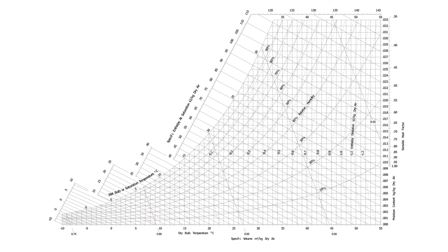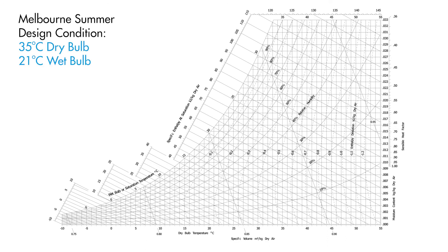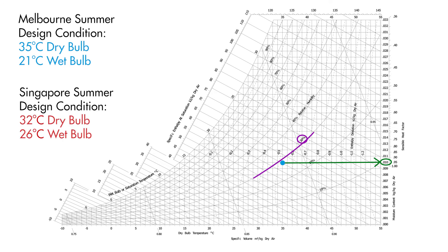Now that we understand these lines of the chart, let's plot the Melbourne summer design condition of 35 degrees dry bulb and 21 degrees wet bulb on the chart. From this point we can immediately see this has a relative humidity of just under 30% and a moisture content of around 10 grams per kilogram of dry air. In comparison, the much more humid Singapore design condition of 32 degrees dry bulb and 26 degrees wet bulb has a relative humidity of a bit over 60% and a moisture content of around 19 grams per kilogram of dry air.